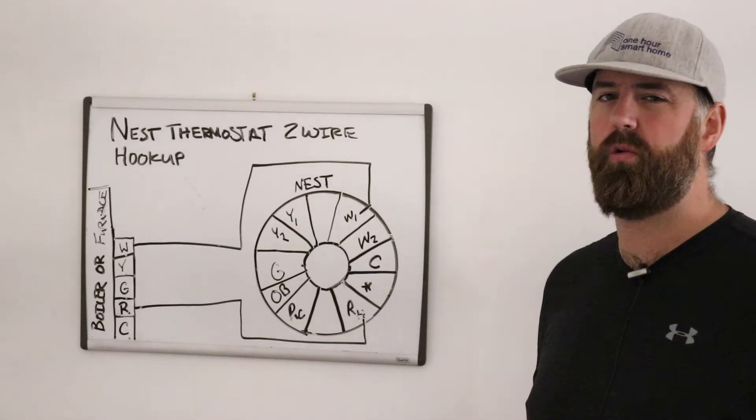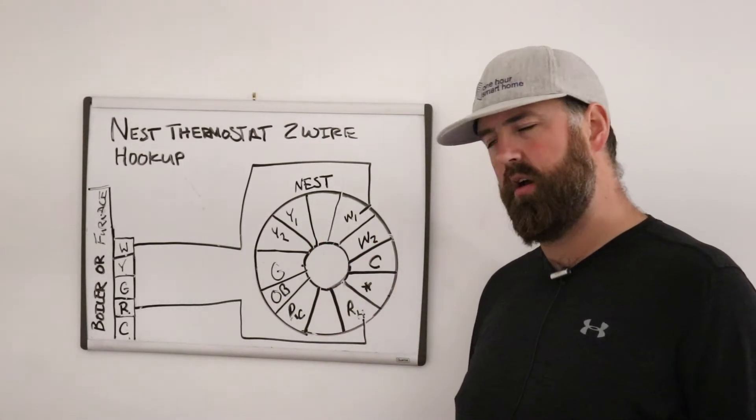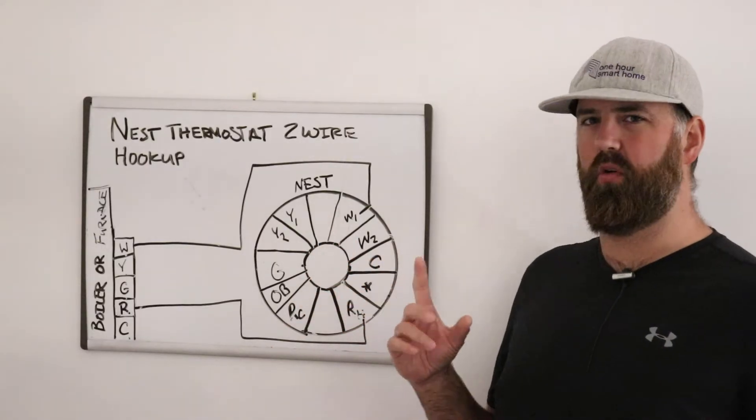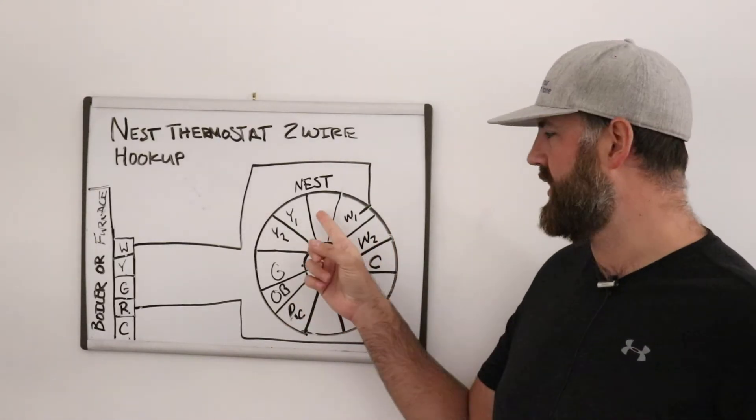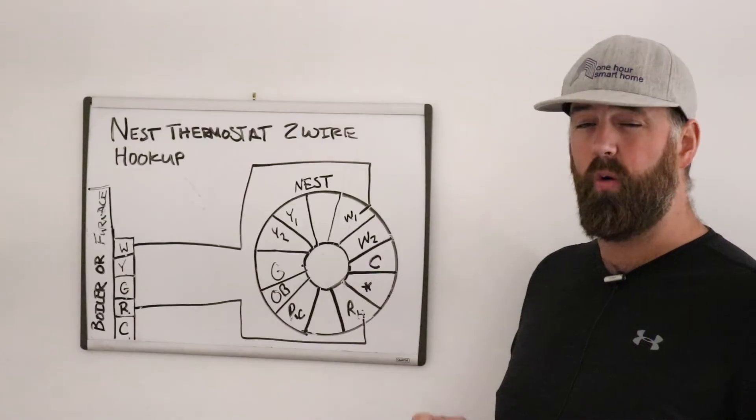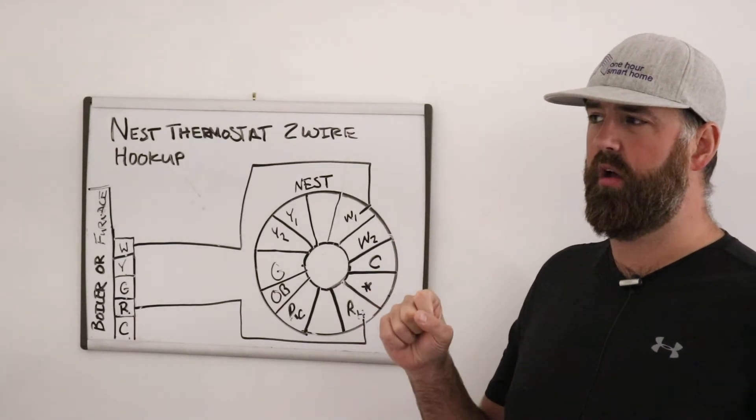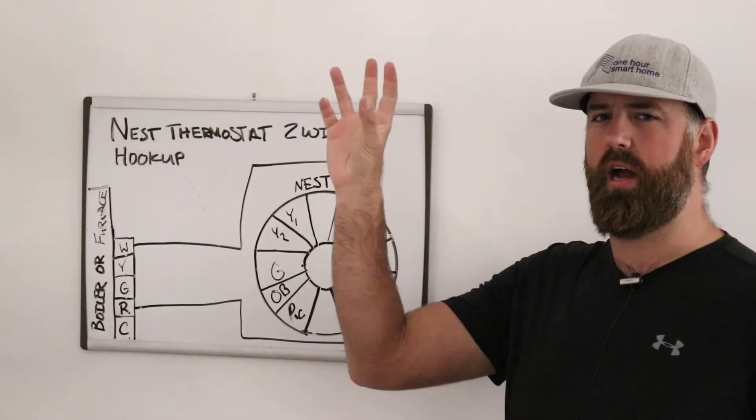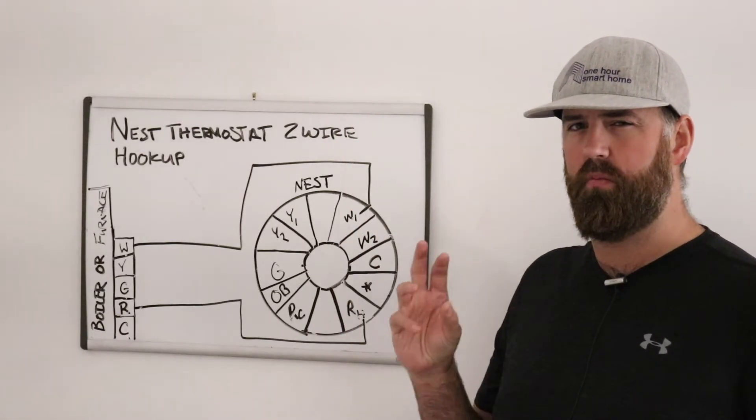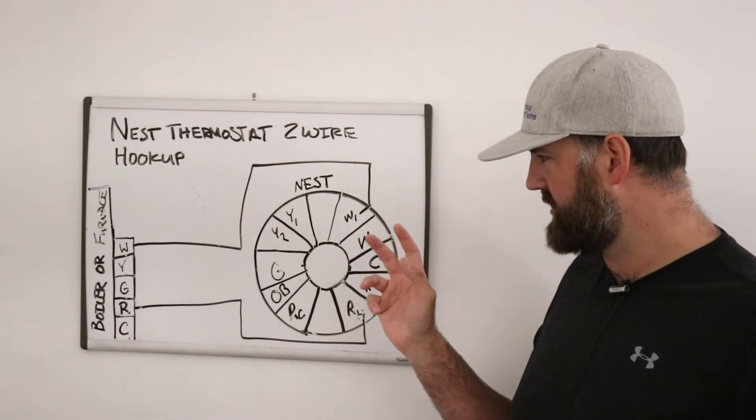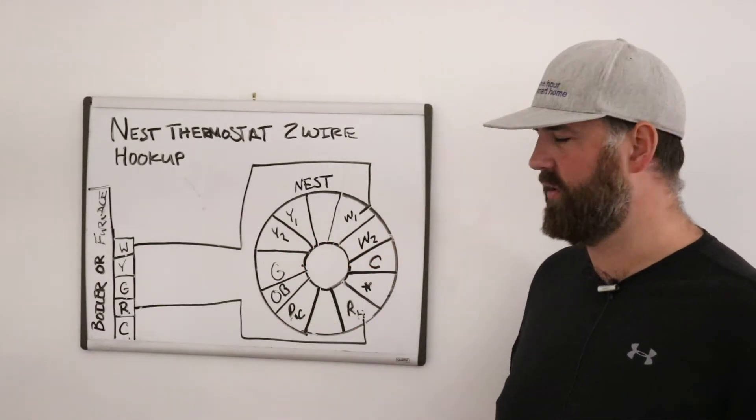Y1, that is cooling. That is a call for air conditioning. Y1 is if you only have single stage cooling you are only going to have one wire there. Y2 is if you have two stage cooling. So that means that you have a second higher stage of cooling. It delivers more cool air faster. It's basically just two speeds for your cooling.